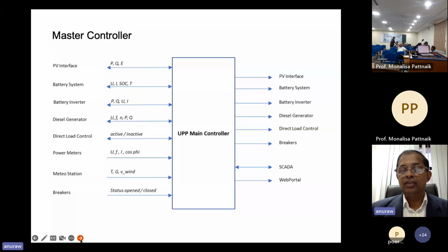The main controller gives commands to different devices on how they should operate. For example, it signals the battery system whether to charge or discharge. When we have excess solar generation, we charge the batteries so we can use that energy later in the evening when solar PV is not available. We'll look at some charging and discharging characteristics in other slides.